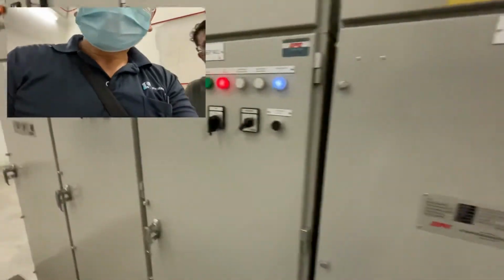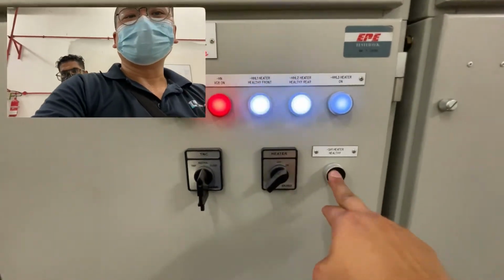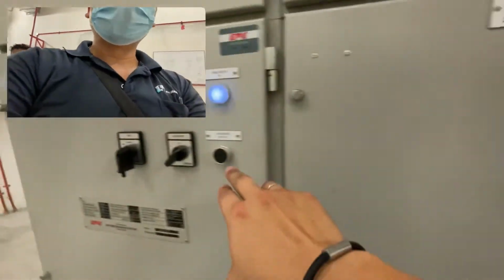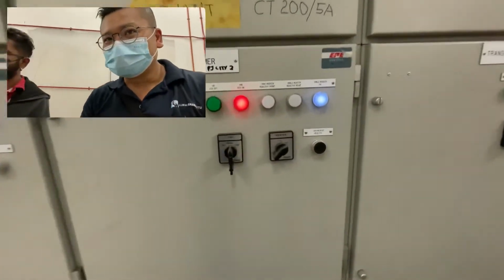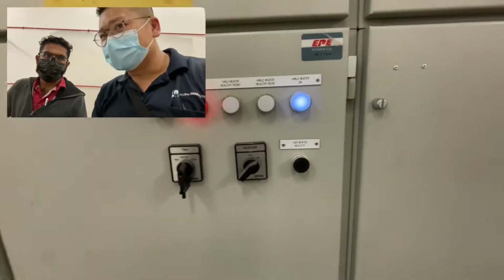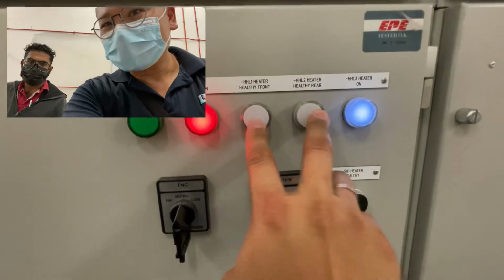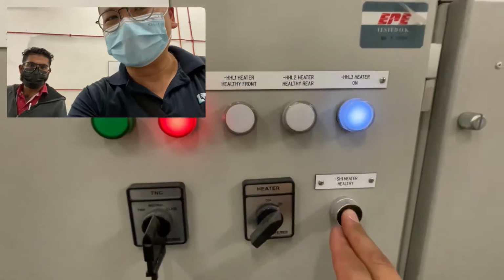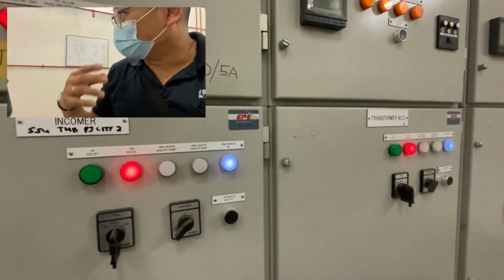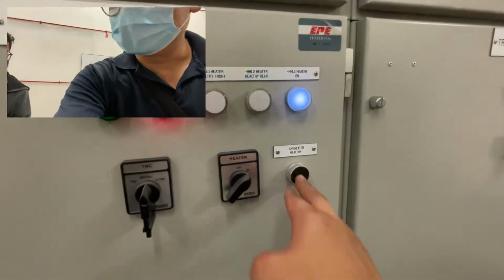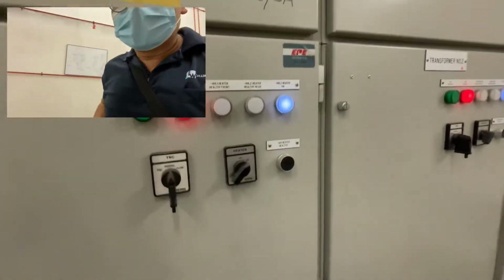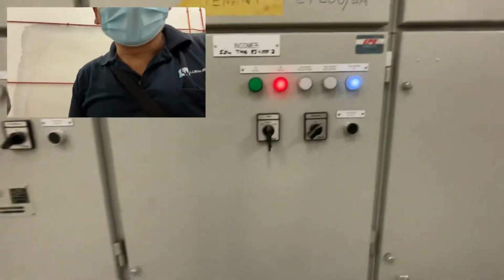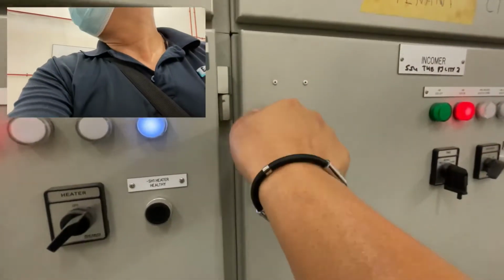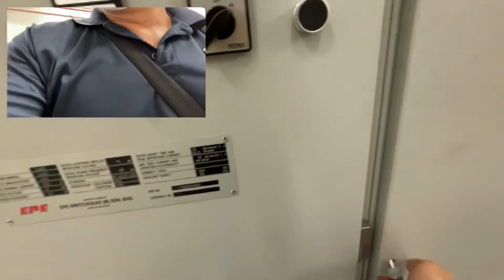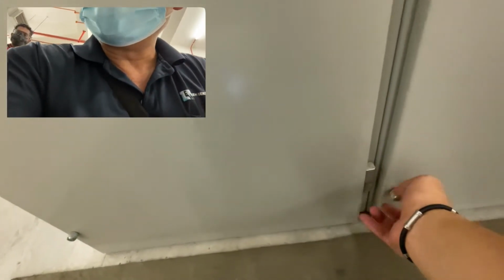For this, you can check whether the heater is healthy or not by pressing here. This light indicates the temperature thermostat is in good condition and there's a relay controlling it. If it lights, it means there's 240 volt going to the heater. But there might be a possibility that the heater is faulty. This only indicates the control is in good condition. Another way is to use a clamp meter to check how many amps at the heater, to truly confirm whether the heater is in good condition or not. If it's in good condition, there will be a current reading.